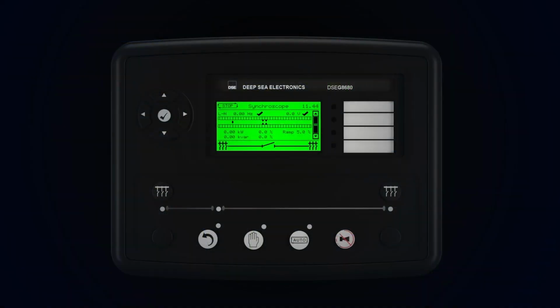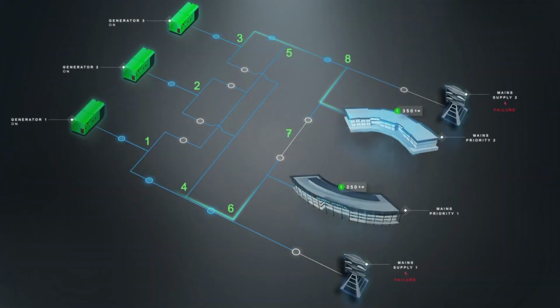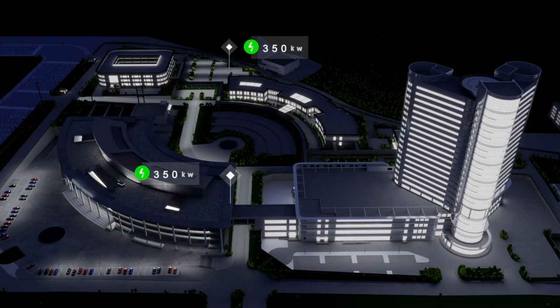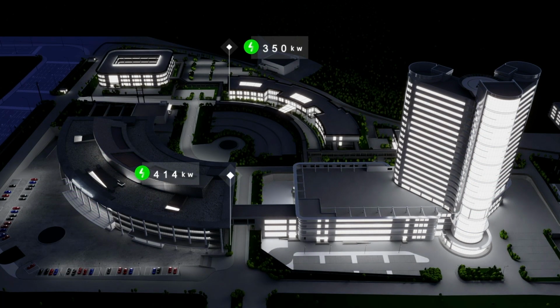All 3 generators now need to synchronize, introducing generator redundancy. Generators 1 and 2 synchronize and breaker 6 closes. Both generators share the attached load. The non-essential load can now be restored. There are currently no redundant generators.